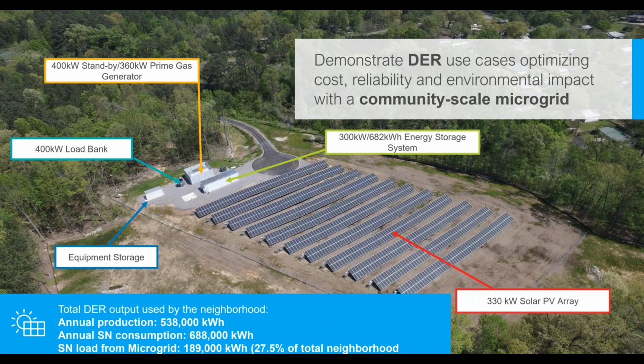Now for the energy storage at 300 kilowatts with 682 kilowatt hours, it should be able to carry the load at peak for a little over 2 hours. But at average load, the energy storage should be able to carry the load for 4 to 5 hours. And with the backup generator, it should be able to carry the load at all times. So that basically summarizes the design, the functionality, and the capacity of our microgrid system.